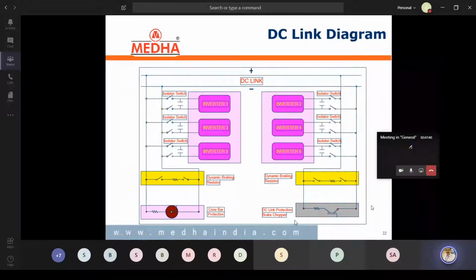Furthermore, across the same DC link there is a brake chopper path with a series resistor and an IGBT module, which we call the brake chopper. Whenever this DC link voltage reaches 2800 volts, the LCC triggers this IGBT with a fixed PWM so that current flows through this additional resistor. This is kept inside the generator room, just back to the TCC. This resistor we also manufacture. It is around 10.65 ohms. Whenever current flows through it, it acts as an additional load and handles the excess voltage, and whenever the DC link comes back within the allowable range, this IGBT will be switched off by the LCC.